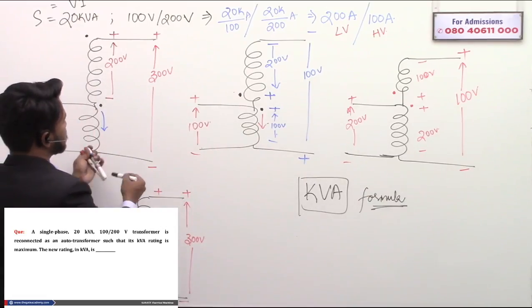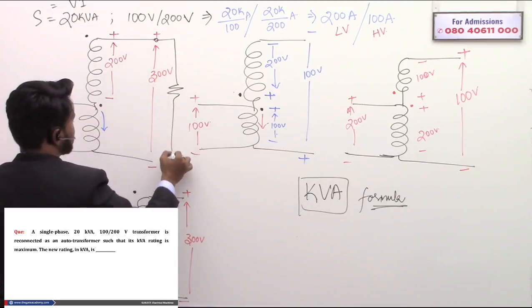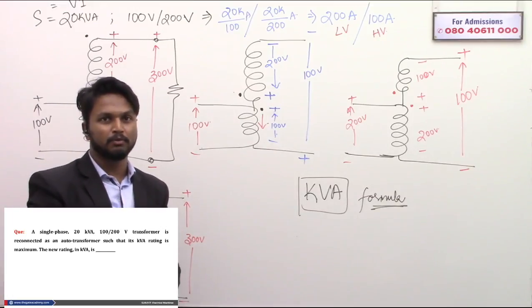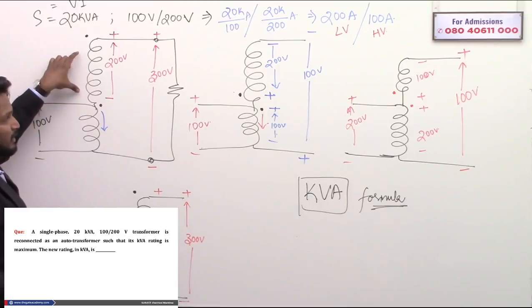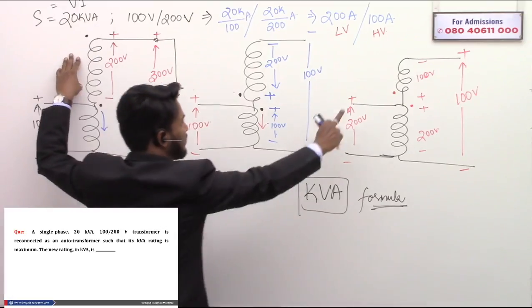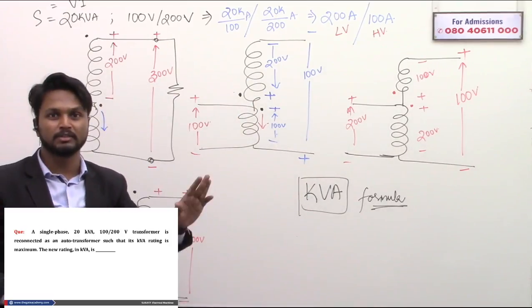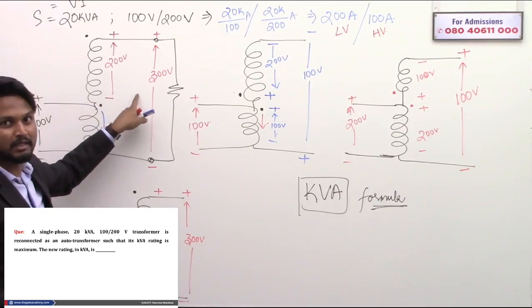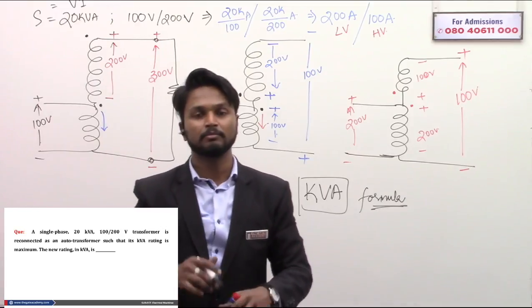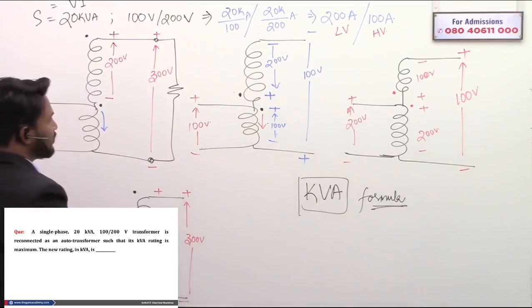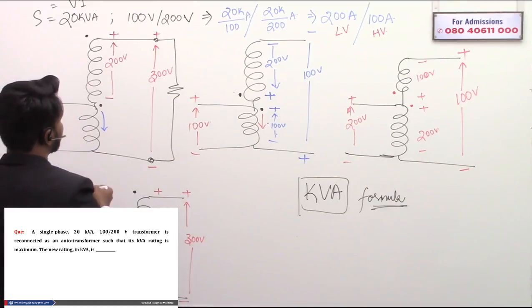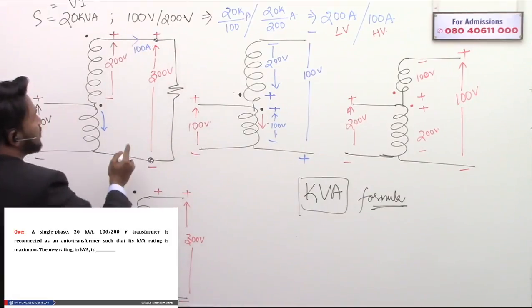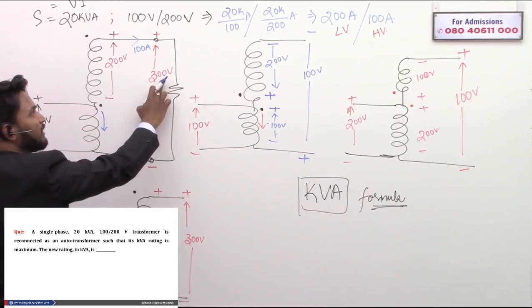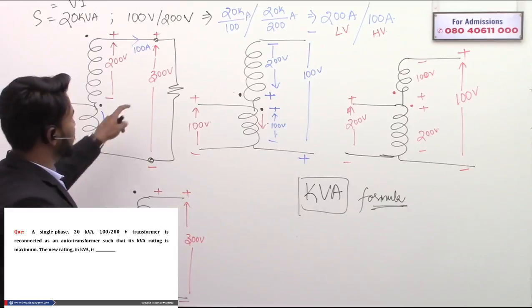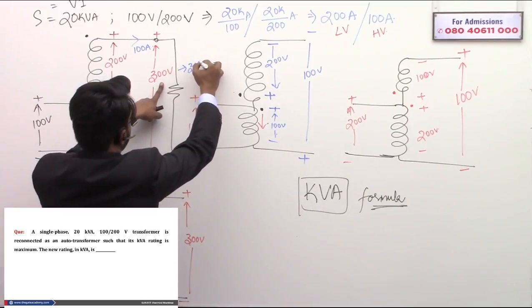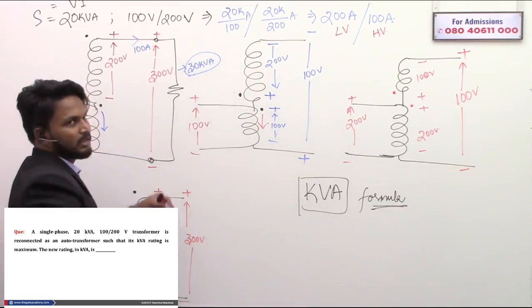See here, if you connect a load across this, let us assume you have connected a load across this, right? And you have fully loaded the transformer. Fully, how much load you can apply on the transformer? Which winding is this? This is HV winding. HV winding current rating is how much? HV winding current rating is 100 amperes. So you can draw a maximum of 100 amperes through this winding, not more than that. So if you draw more than 100 amperes, this winding is going to die. It will become popcorn, meaning it will burn out, right? So you can draw not more than 100 amperes from this particular winding. Therefore the rating of this particular configuration is 300 multiplied by 100. 300 multiplied by 100, how much is it? That is 30 kVA. Rating of this configuration is 30 kVA.